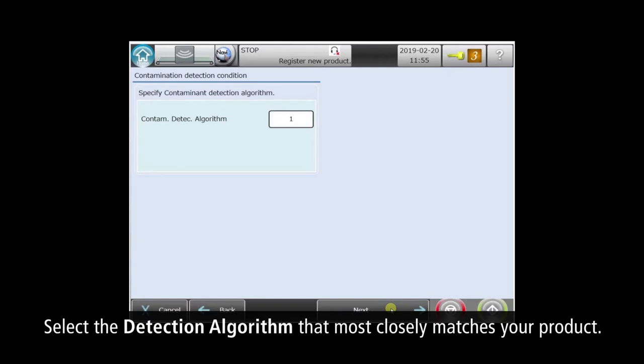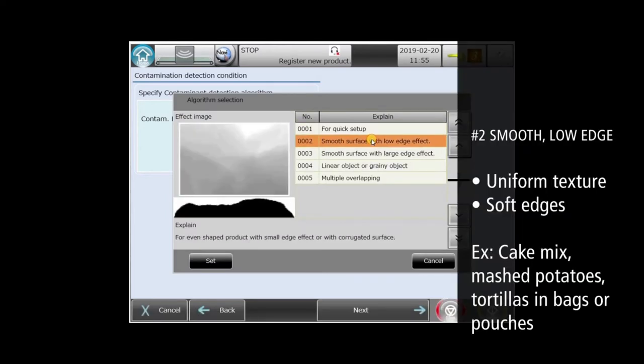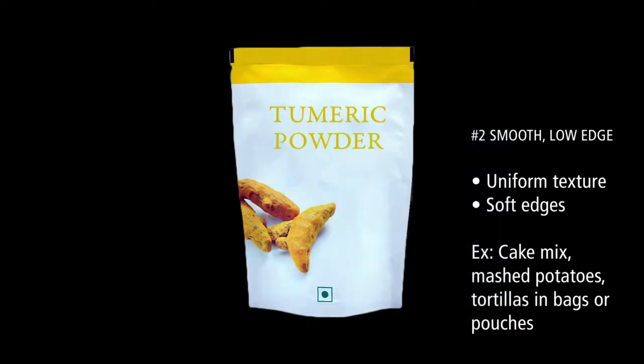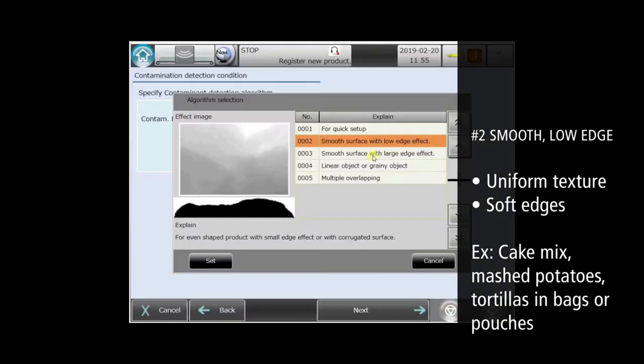The XR75 comes with special detection algorithms that cover the majority of applications. We'll skip number one, which is a legacy algorithm. Number two is for smooth products with soft edges, like powders and pouches. Notice how the example X-ray images reflect this product type.